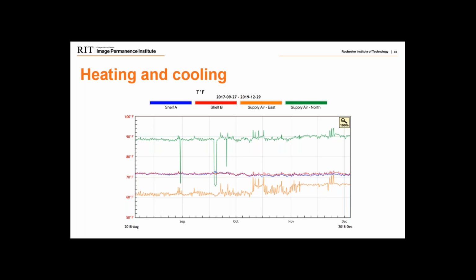When we really started to collect this data, even walking around first with an IR camera, we were able to identify that one side of the room was being heated, one duct coming from one side was heated, and the ducts from the other side were being cooled. They actually mingled throughout the space, alternating down the aisle. So as that air mixed, you really couldn't tell what was going on until you looked at the data.